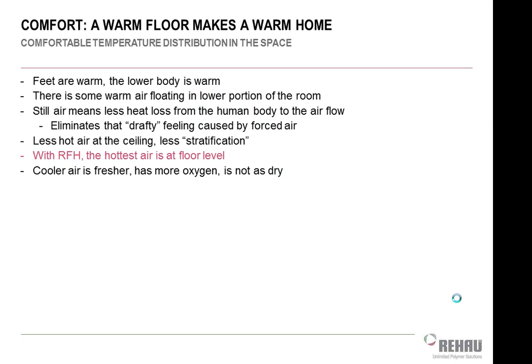The other thing is by not having very much air movement in the space, I'm able to reduce drafts. And in the heating season, that's very beneficial because having air move across your body takes heat away from your body, which makes you feel cooler. If you don't have any air, you don't feel that. In commercial buildings, you're still going to have a little bit of air because you have ventilation codes to satisfy, but you'll have much less air than you would in a forced air system when you have a radiant system.